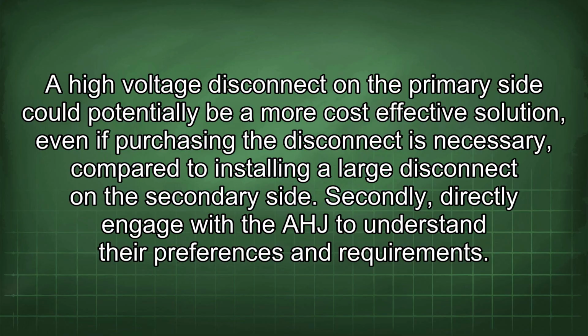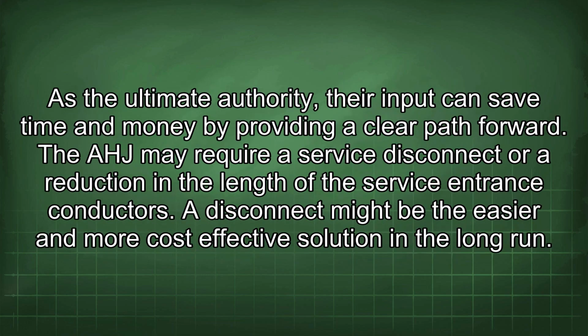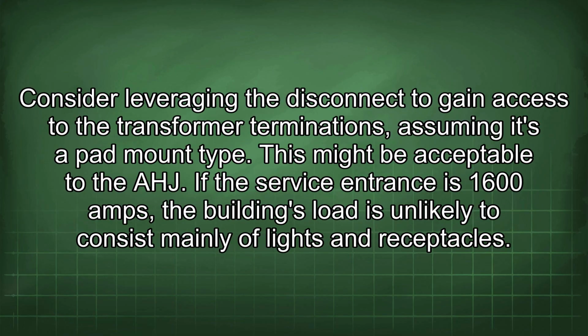Secondly, directly engage with the AHJ to understand their preferences and requirements. As the ultimate authority, their input can save time and money by providing a clear path forward. The AHJ may require a service disconnect or a reduction in the length of the service entrance conductors. A disconnect might be the easier and more cost-effective solution in the long run. Consider leveraging the disconnect to gain access to the transformer terminations, assuming it's a pad mount type. This might be acceptable to the AHJ.